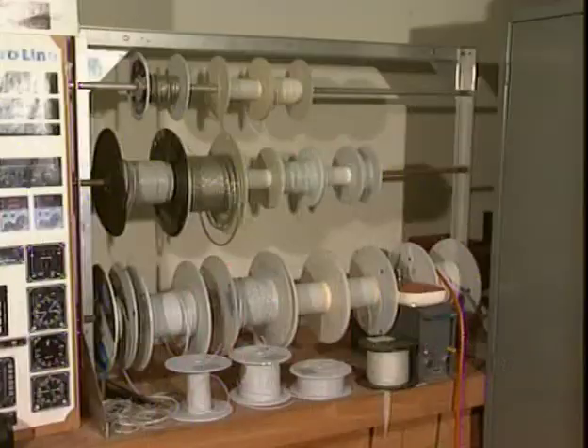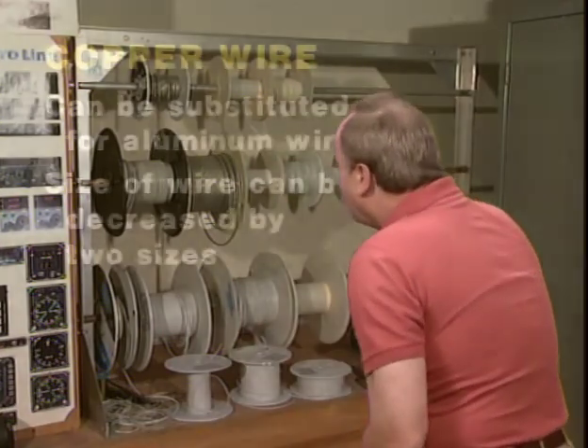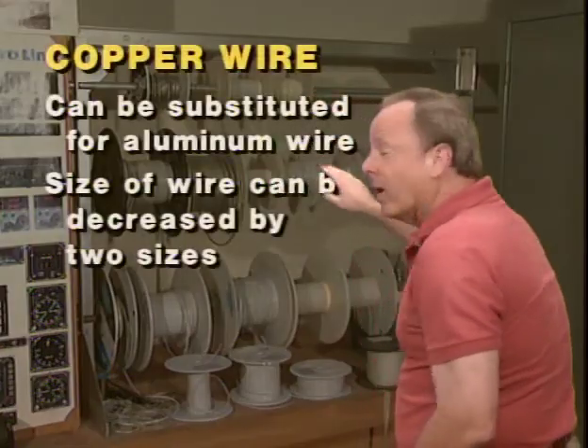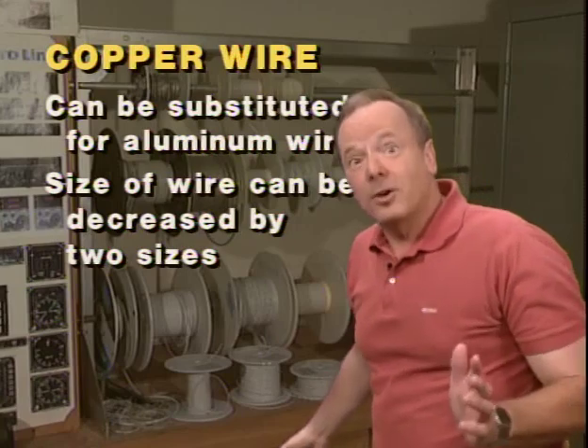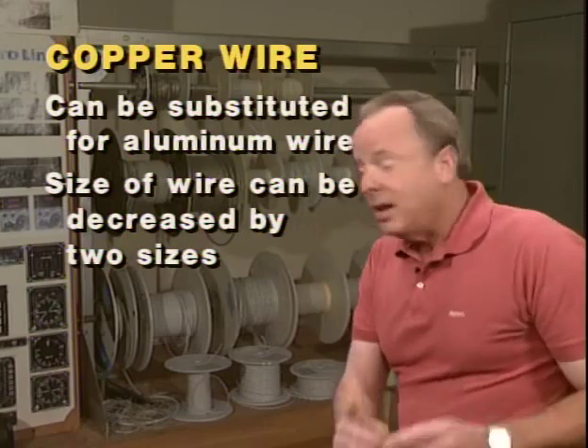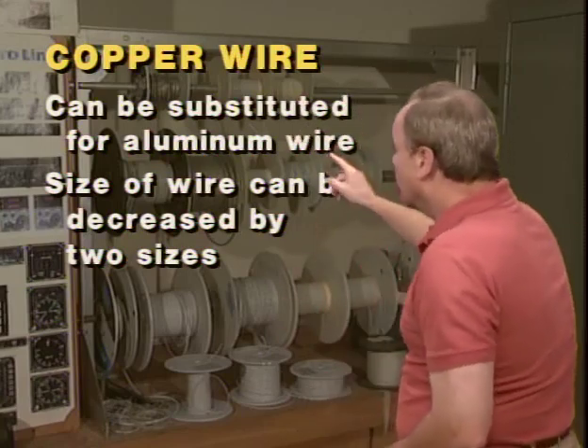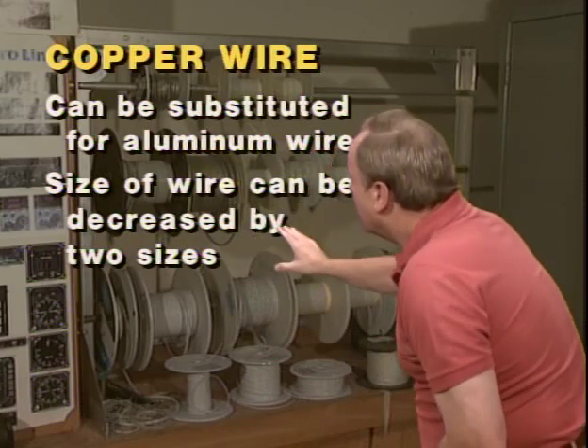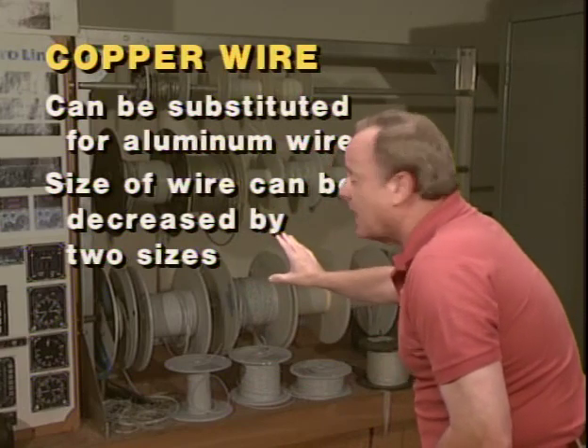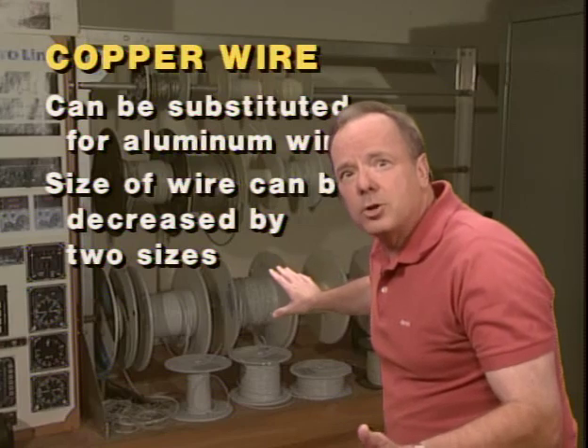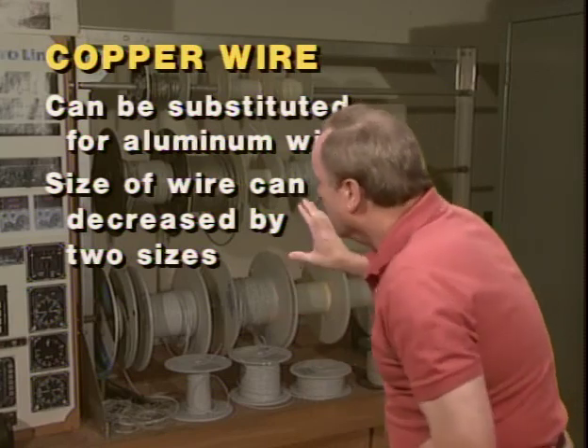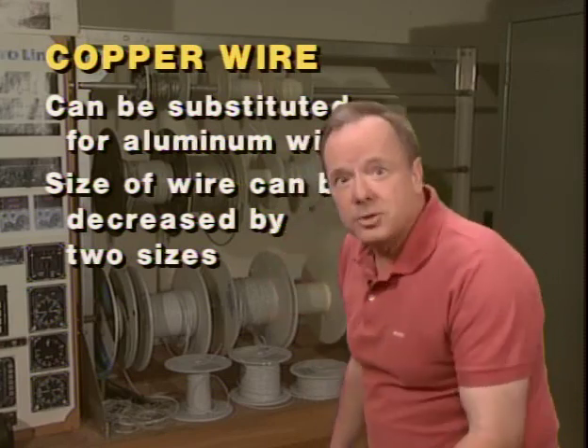Now, if you find an aircraft with aluminum wire in it, you should know that copper wire can be substituted for aluminum wire. Not only can it be, I think it's a darn good idea too. Not only that, if you do substitute copper wire for aluminum wire, you can decrease the size by 2 sizes. And as you well know, that means you go up in gauge number. When you decrease the wire size, the gauge number goes up.